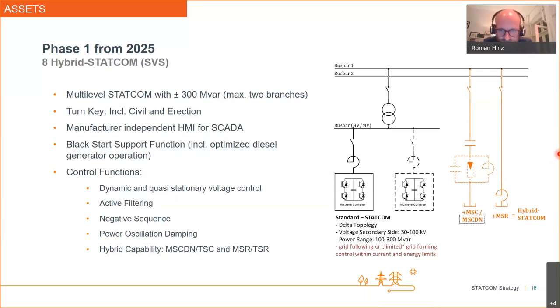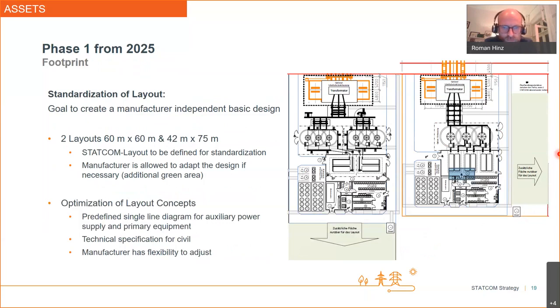So, yeah, you can also go to the next slide then. As I told you, we try to align the different manufacturer designs. So we had several meetings with the manufacturers who are supplying these kind of converters. And our goal as a TSO, for sure, as I told you before, is to standardize as much as possible. And usually in our substations, we do not have much space to install those STATCOMs, because they are usually situated near cities and other places in Germany where you do not have the possibility to buy new land to add STATCOMs to your substation. So we usually have only 60 by 60 meters as one footprint, or the other option, 42 by 75 meters. These are our usual footprints we plan right now for our STATCOMs.